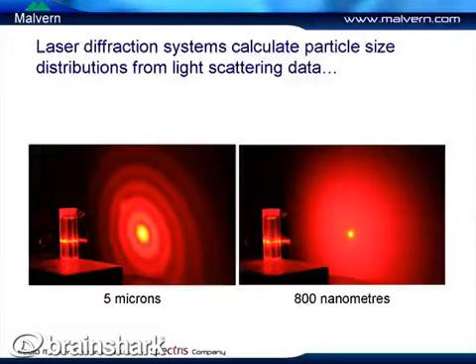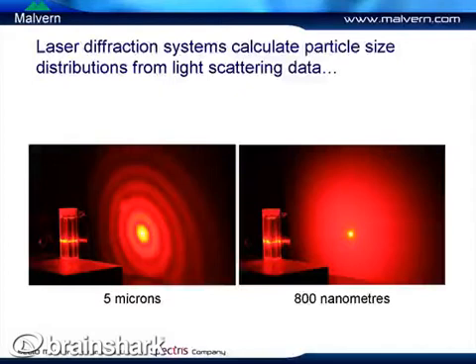We can see light scatter from particles at both 5 microns and 800 nanometers particle size, in this case in a simple cuvette. Laser diffraction measures the intensity profiles we see for these particles. By measuring the change in intensity as a function of angle, we can interpret that as a particle size distribution, and in order to do that, we need an optical model of some kind.